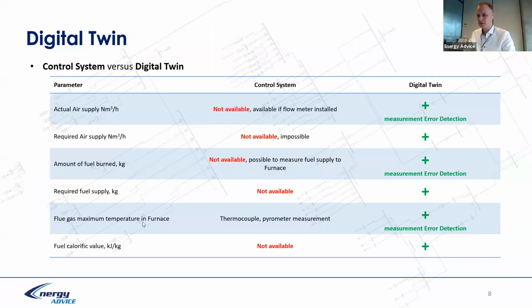Another one is the flue gas maximum temperature in the furnace. In fact, the control system knows this because it has thermocouple or pyrometer measurement devices. But in our expertise, the pyrometer or thermocouple could be installed in a bad place, and the flue gas temperature in the furnace could be higher or lower than the measured value. So the digital twin allows us to calculate and detect the error of a measurement. Fuel calorific value is absolutely impossible in the control system, I mean for biomass boilers. But the digital twin allows us to do this.